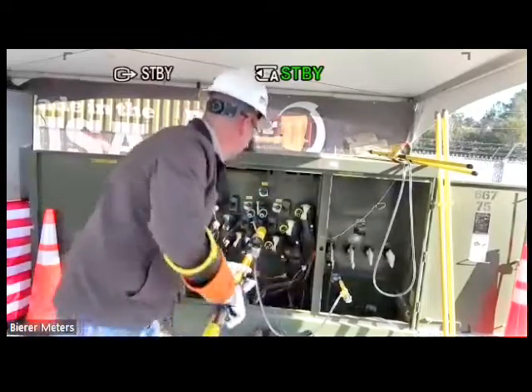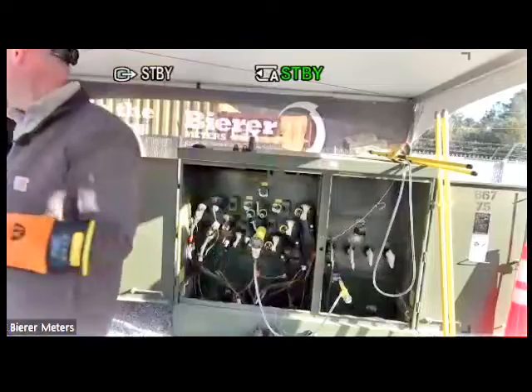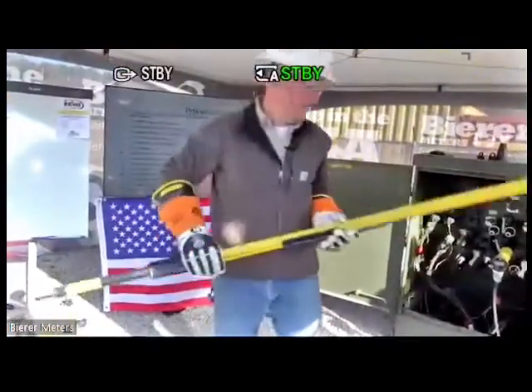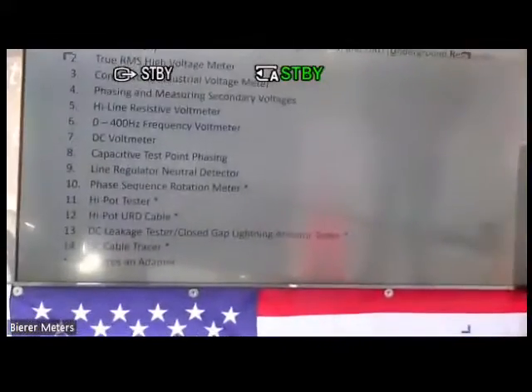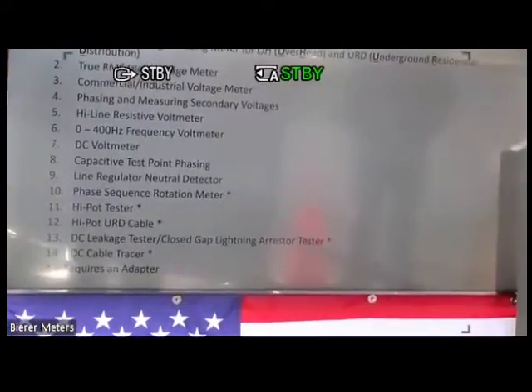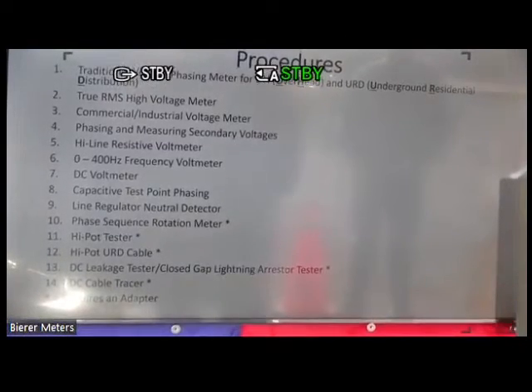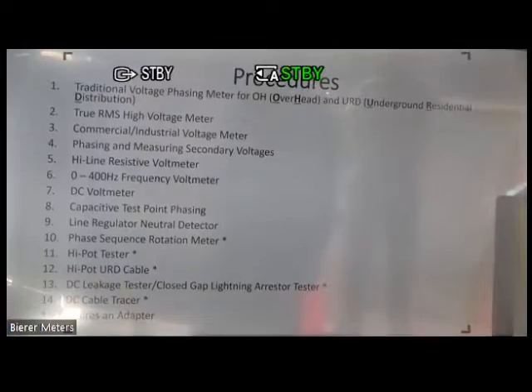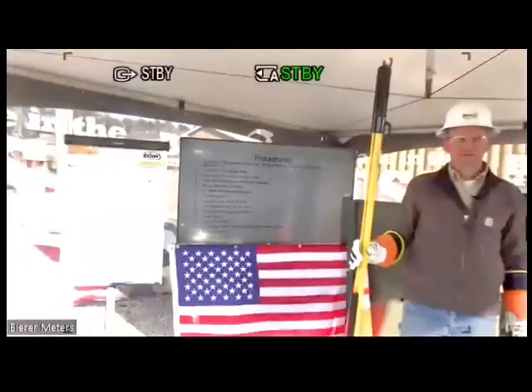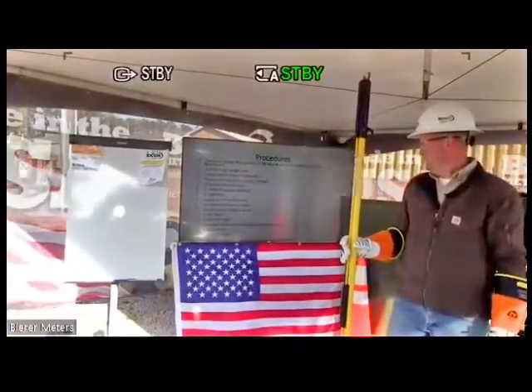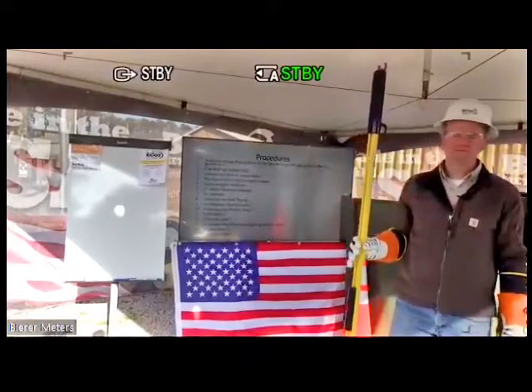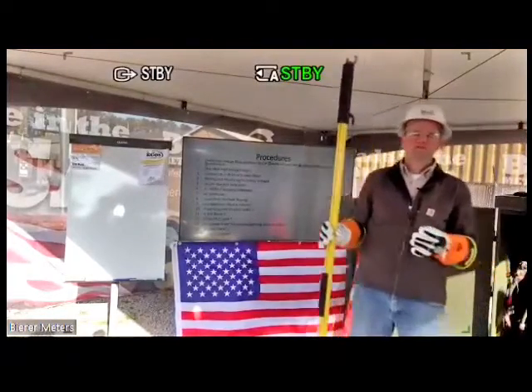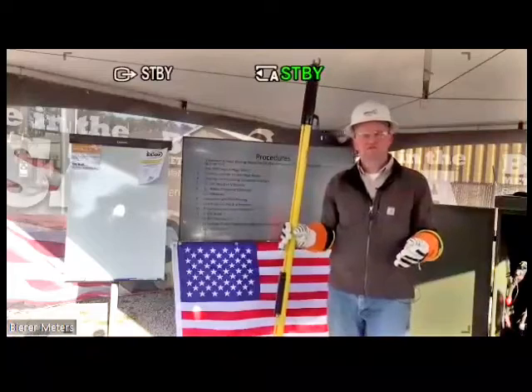All right, so that's one. The lightning arrestor, we don't actually have a bad lightning arrestor here. We do have one up on the pole, so we won't be able to actually demonstrate that, but we will high pot the URD cable. So the one right above it, where we high pot the URD cable, again, you're essentially high potting the arrestor.